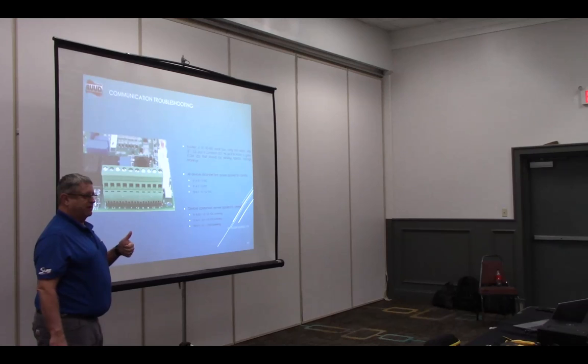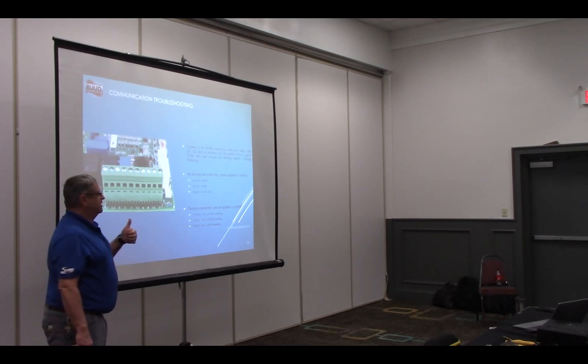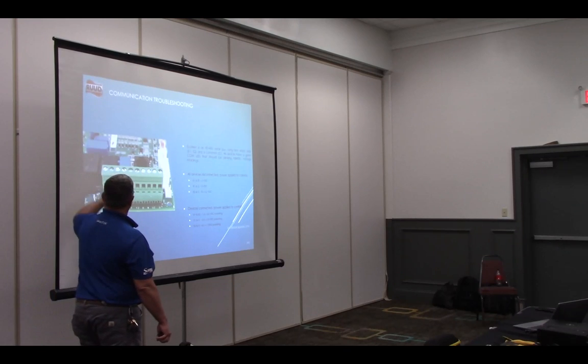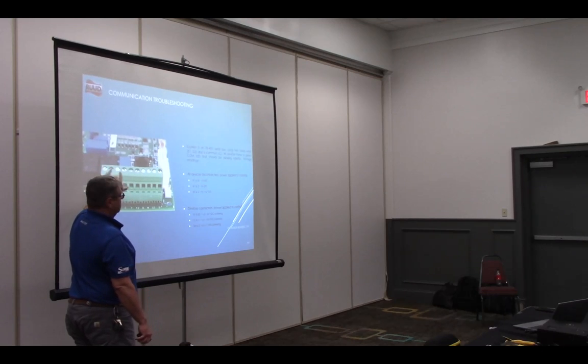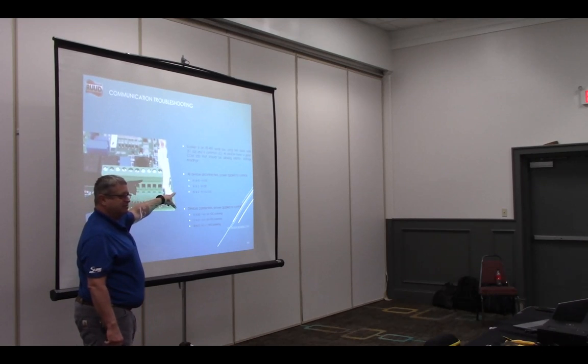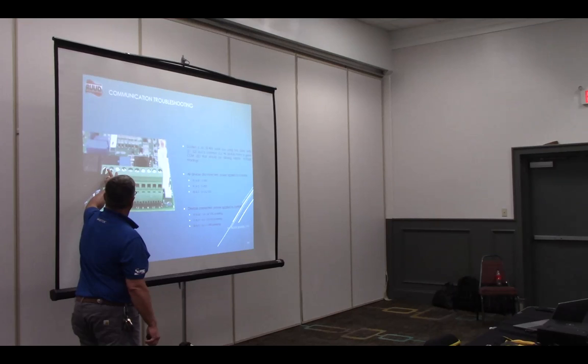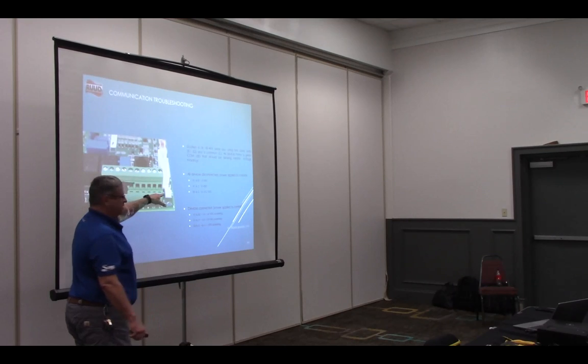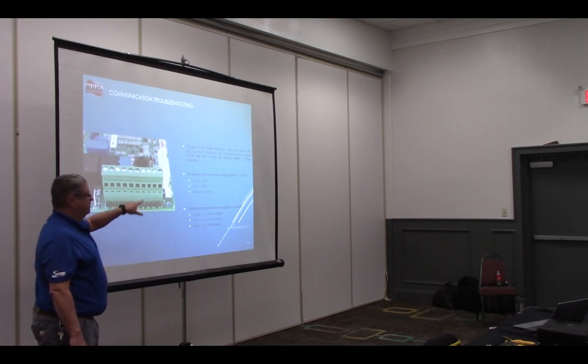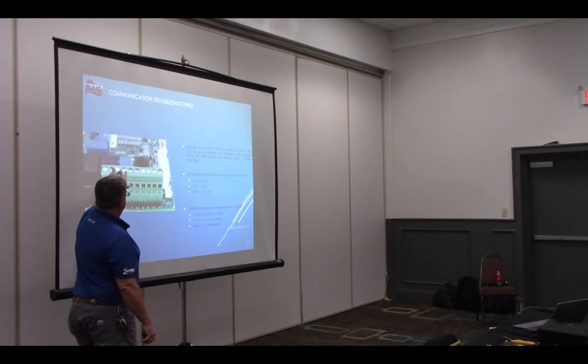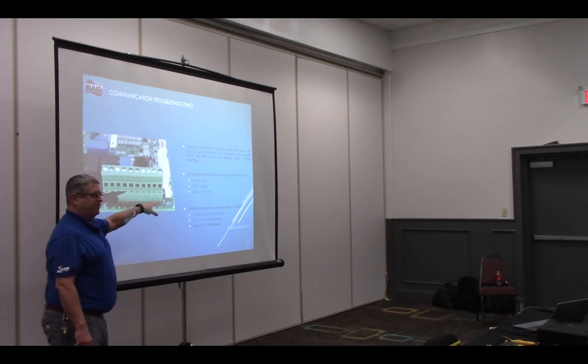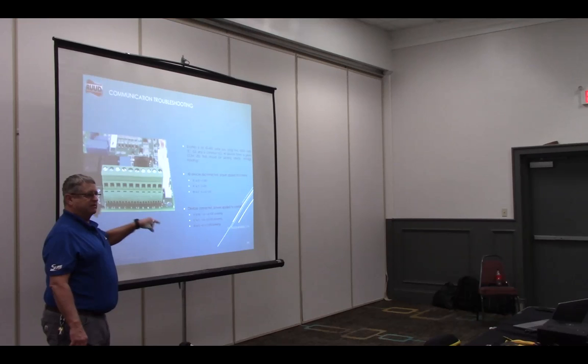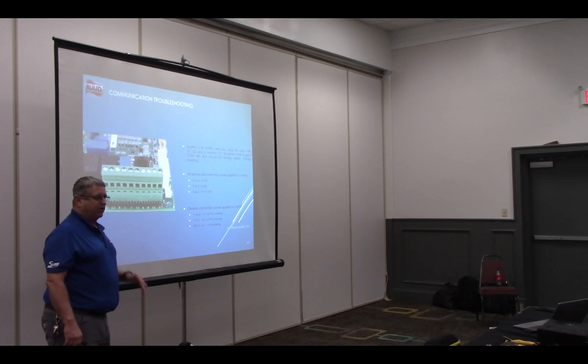We're going to take our meter out. We're on DC volts, and we're going to check between E1 and E2 on the board. We should have 3 volts DC. We'll go between E1 and common. We should have 3 volts DC. We're going to go between E2 and common. We should have basically nothing. That tells us the board is good. We know our board is good then, okay?